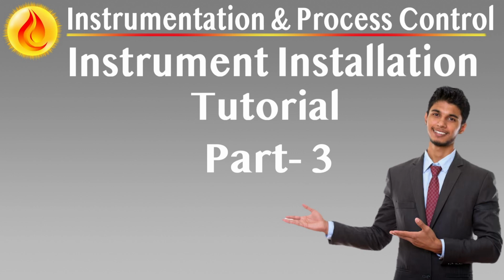Limitations and maintenance demands. Why purging is a last resort. Despite its effectiveness, external purging is maintenance intensive and should only be used when simpler solutions such as heating, seal fluids, or self-purging geometry are impractical. Over time, purge systems are prone to issues such as flow rate drift, check valve failure, or inadvertent supply interruption, all of which can cause measurement errors or process upsets. To mitigate these risks, purge systems should be installed with pressure indicators or flow monitors to provide early warning of failure. Regular inspection and cleaning of filters and valves are required to maintain purge performance.